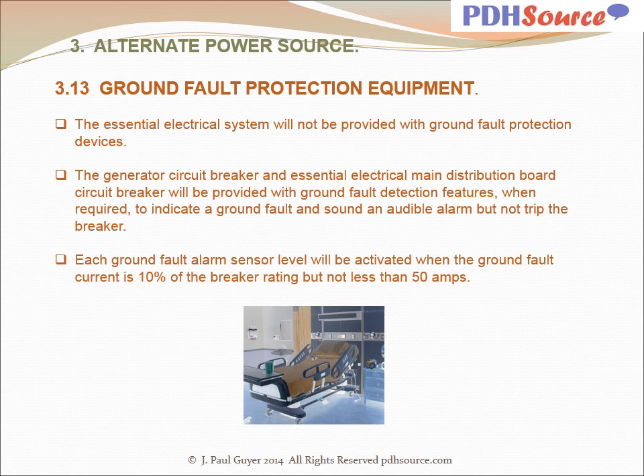The essential electrical system will not be provided with ground fault protection devices. The generator circuit breaker and essential electrical main distribution board circuit breaker will be provided with ground fault detection features when required to indicate a ground fault and sound an audible alarm but not trip the breaker. Each ground fault alarm sensor level will be activated when the ground fault current is 10% of the breaker rating but not less than 50 amps.